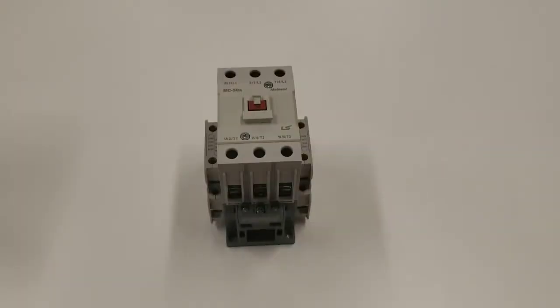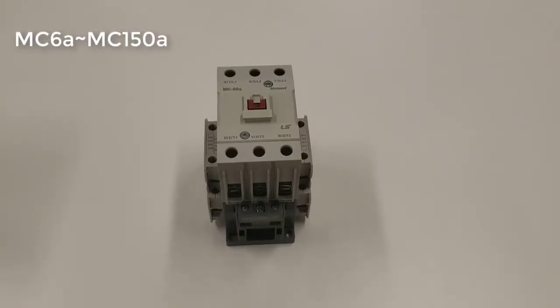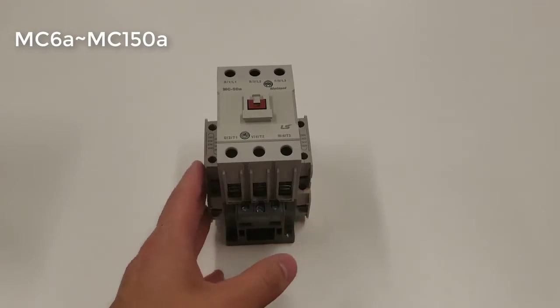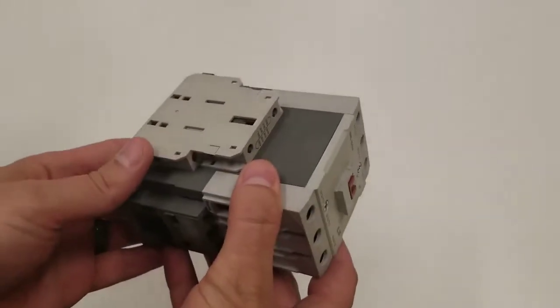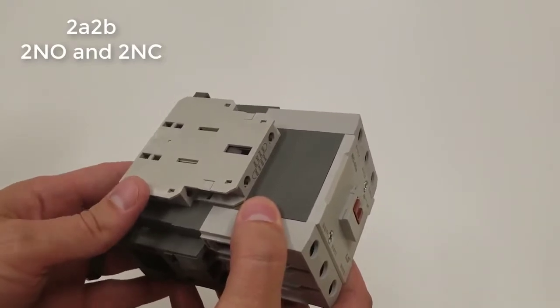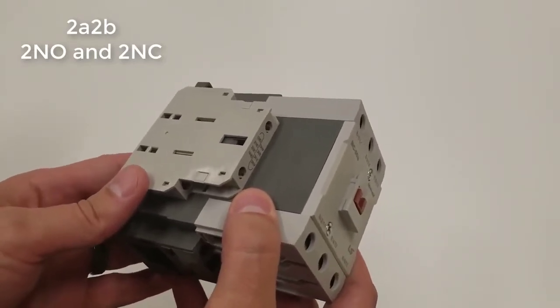In this video we're going to show how to add and remove auxiliary contacts onto the MC type contactors. The first thing we're going to show you is up to 150 amp frame. You could easily remove the auxiliaries. So our standard stock in the US is a 2A, 2B. So that means two normally open and two normally closed.